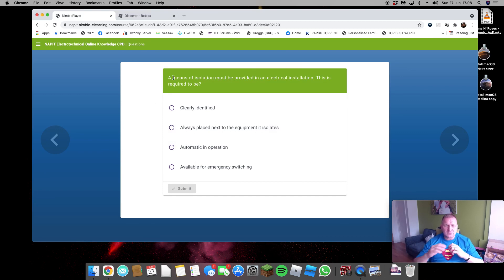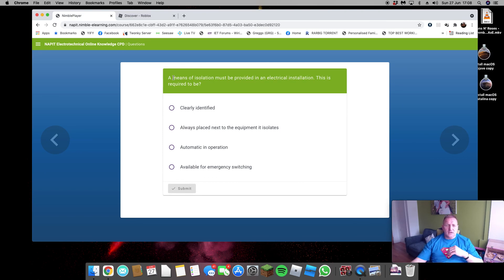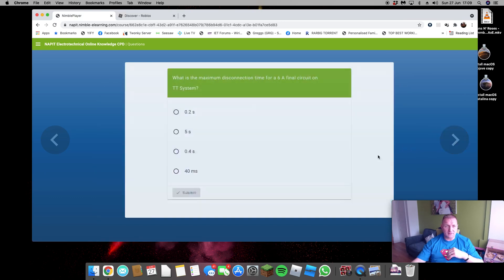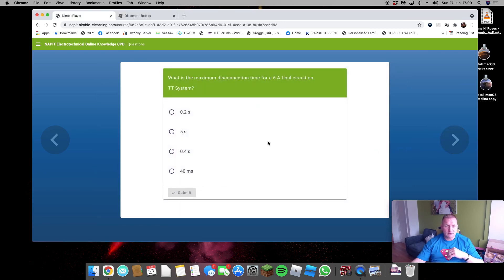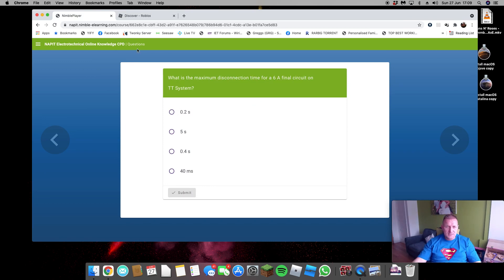Means of isolation must be provided in electrical installation. This is required to be clearly identified, of course. Sticker on the bloody thing. What's the maximum disconnection time for a 6 amp final circuit on the TT system? 0.2 of a second.